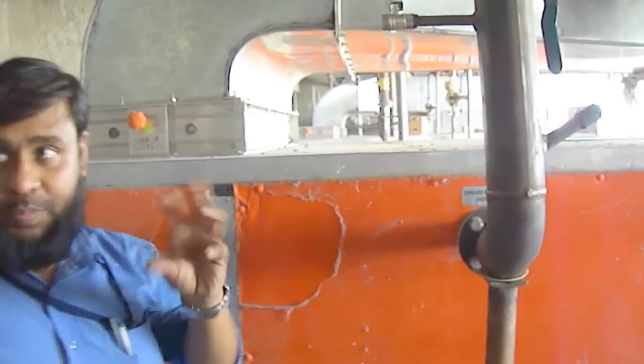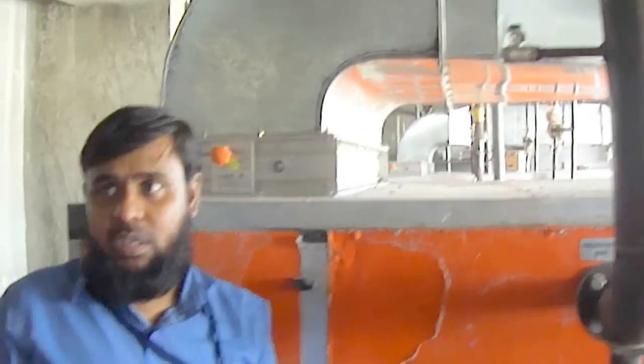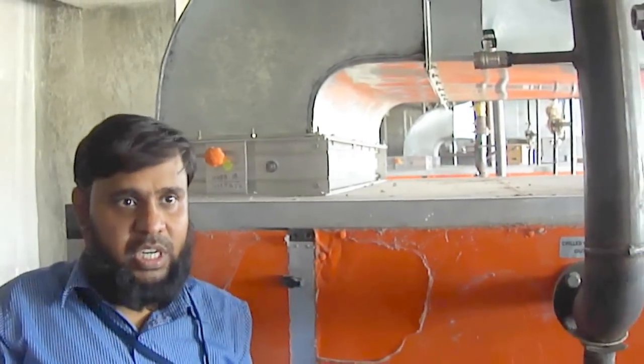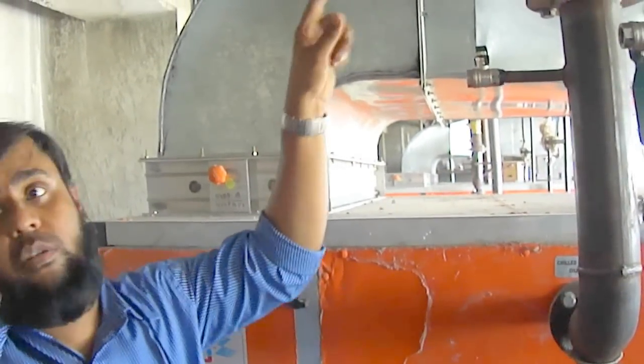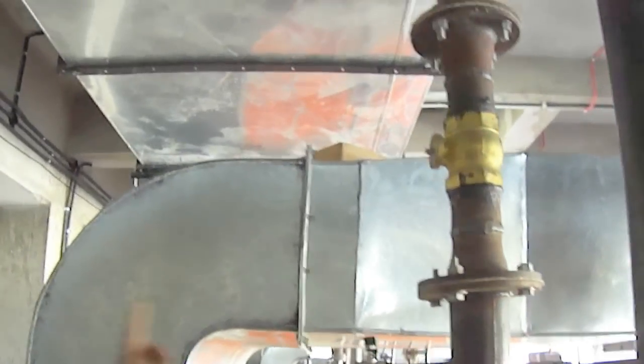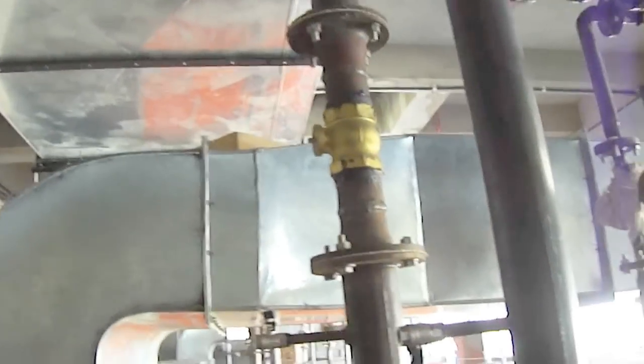And when it is set to minimum, this line will send back pressure. So whenever this line sends back pressure, the motor speed is automatically controlled, because in the plant room just now we have seen the VFD, the secondary pump is a variable frequency drive. Fine. So that is the importance of two-way. So whenever you get a two-way valve, you think that it's a variable flow system. Fine. Three-way means constant. In case of three-way, you can see it for hot water.